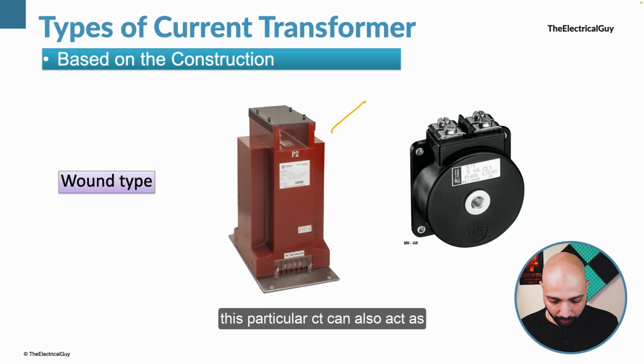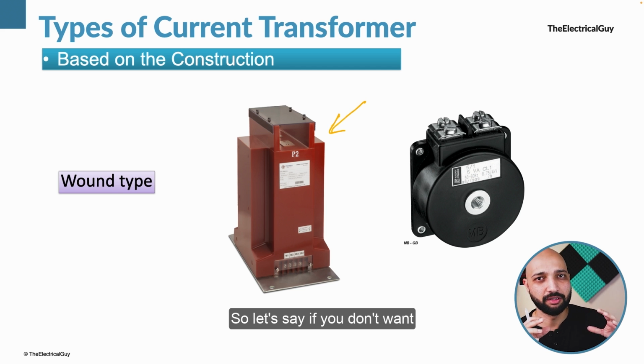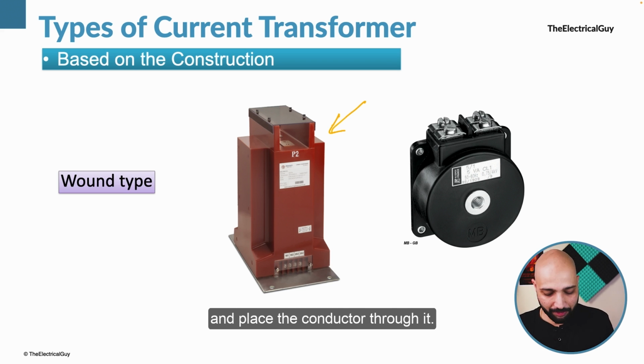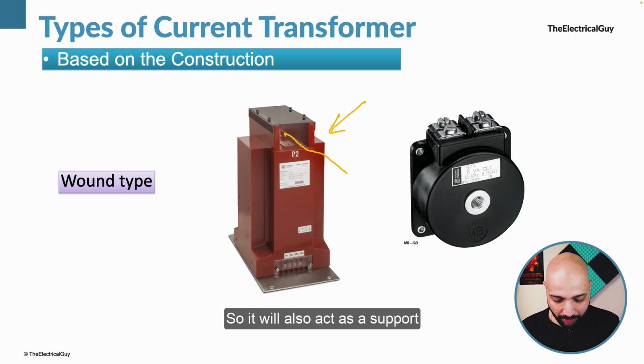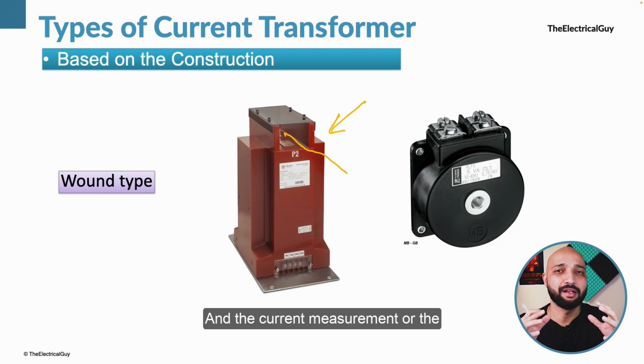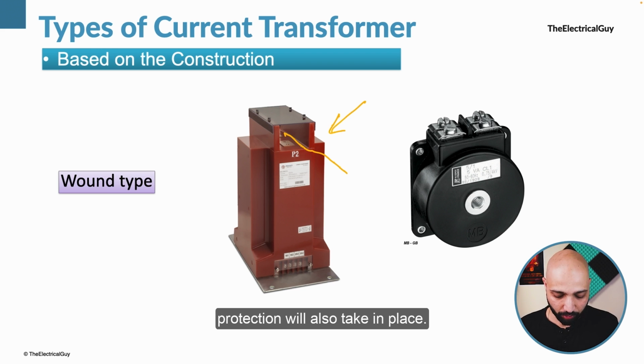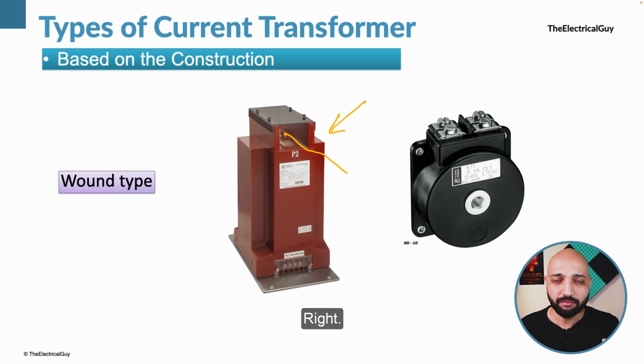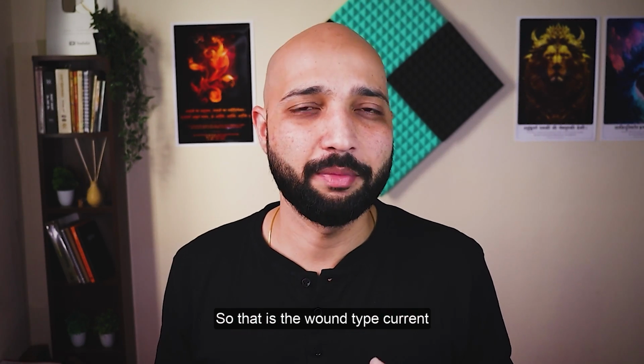Now, this particular CT can also act as a support for the conductor. So let's say if you don't want to use a dedicated bushing, you can use this current transformer and place the conductor through it. So it will also act as a support to the conductor, and the current measurement or the protection will also take place. Right? So that is the wound type current transformer.